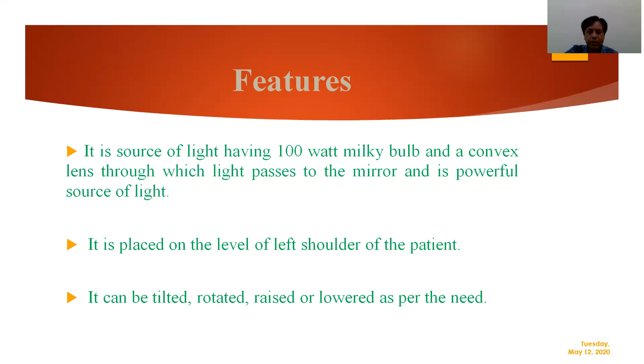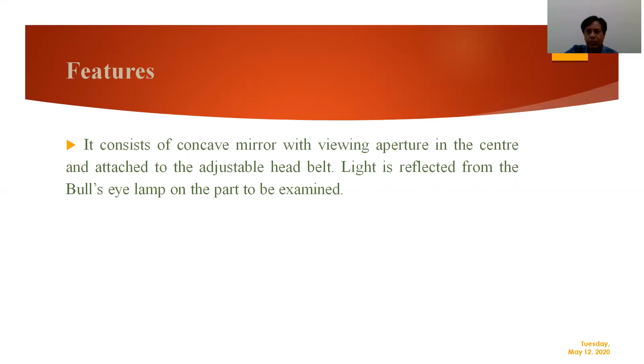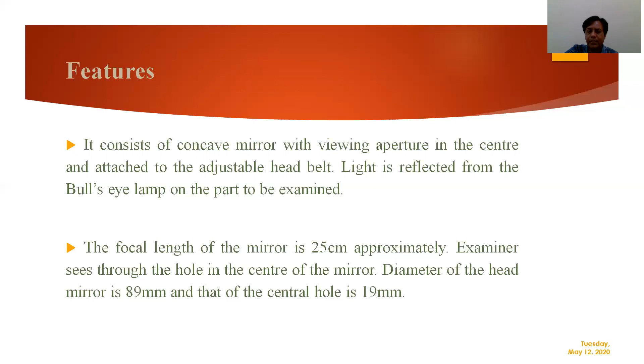The mirror is a concave mirror with a hole in the center, attached to an adjustable head band. Light is reflected from the bullseye lamp onto the part to be examined, either ear, nose or throat. Here we are discussing examination of ear. The focal length of the mirror is approximately 25 centimeter. Examiner sees through the hole in the center of the mirror. Diameter of the head mirror is 89 mm and that of the central hole through which we see is 19 mm.